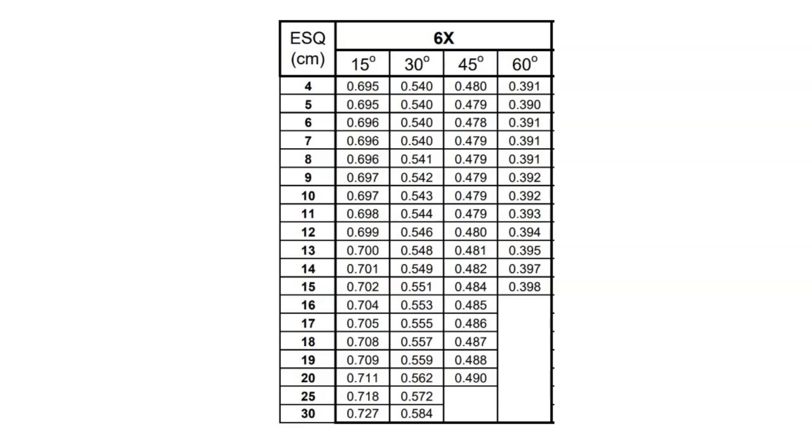Another thing you should notice is that some field sizes don't have wedge factors defined for these larger wedge angles. That's because at some point you're limited by the weight and bulkiness of the wedge. With these thicker wedge angles, you'd need a lot of material to cover the entire field, so you're kind of getting a small workout lifting and clipping these wedges into the treatment head. They actually have limited field sizes because of that.